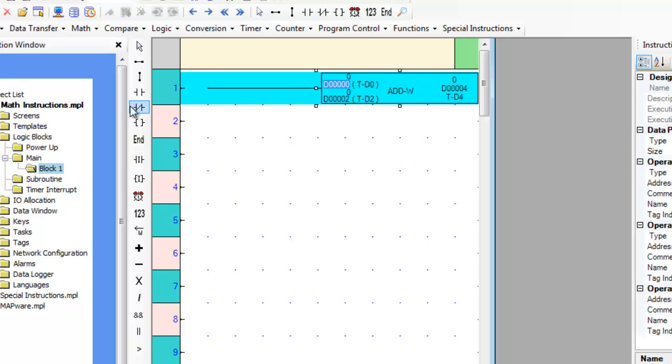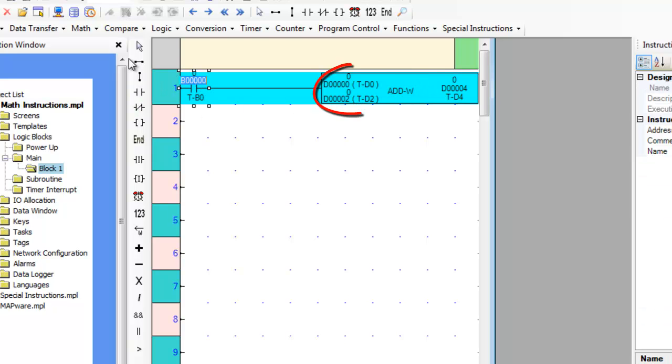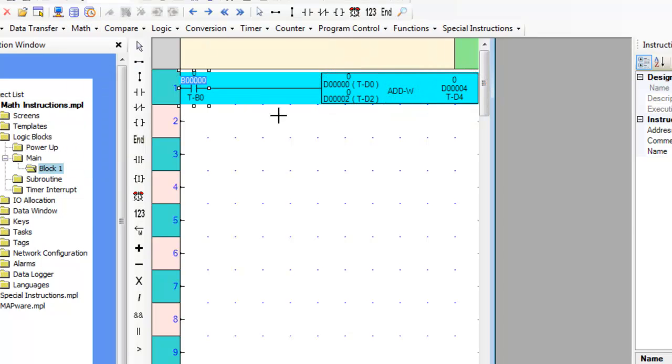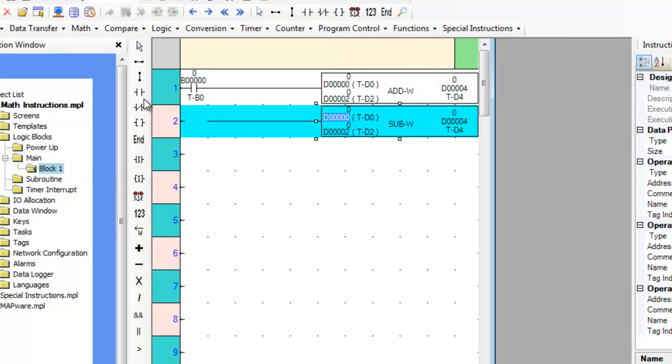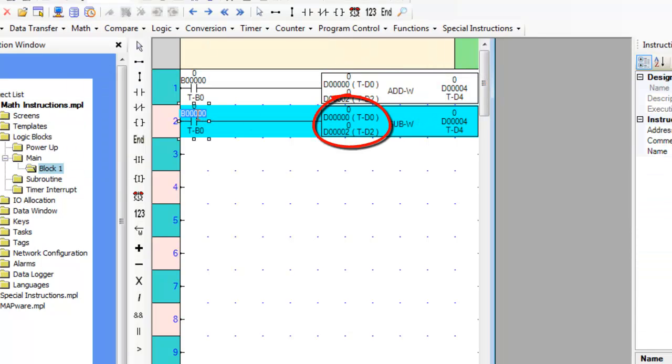The addition instruction adds together the values in registers A and B when the rung is true and the sum is placed in register C. The subtraction instruction subtracts the value in register B from register A when the rung is true and the result is placed in register C.